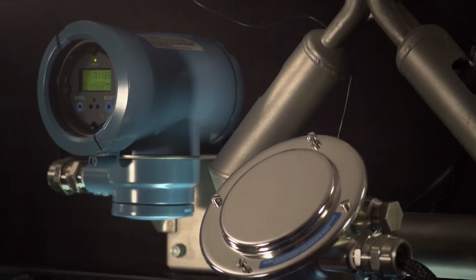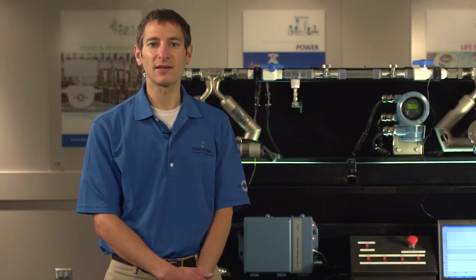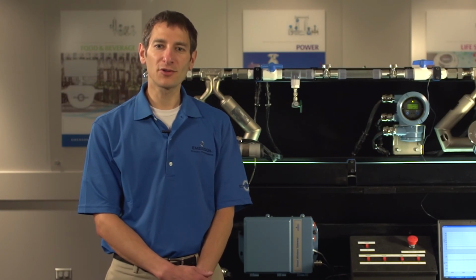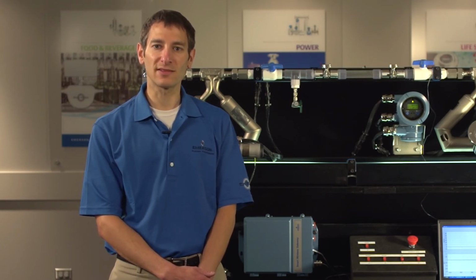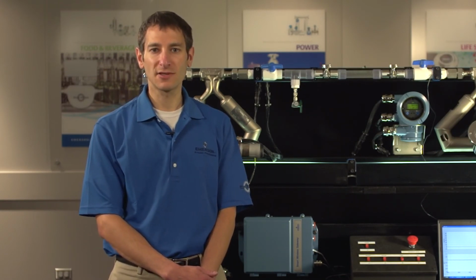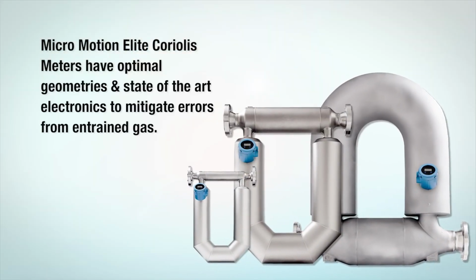All flow meters have problems with entrained gas. For example, turbine meters can overspin and cause damage. All volumetric meters over-report by at least the amount of entrained gas. For example, a volumetric meter over-reports liquid quantities by 5% if 5% gas volume fraction exists in the pipeline. Elite Coriolis meters have the optimal geometries and state-of-the-art electronics to be able to mitigate errors caused by lower levels of entrained gas.